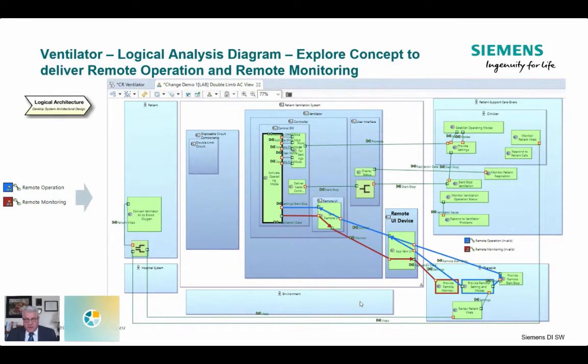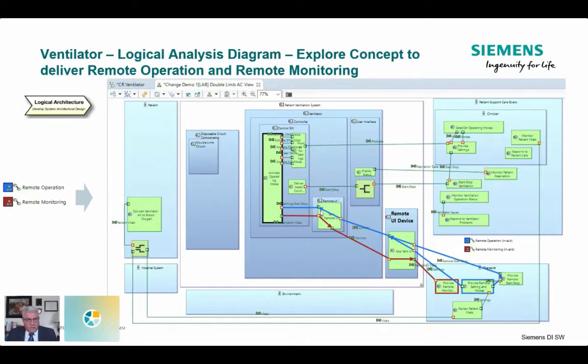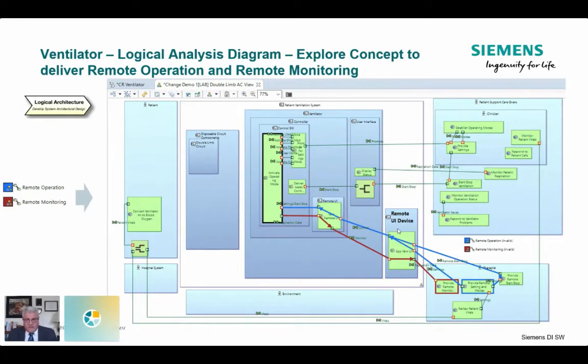Those system functional chains — remote operation and remote monitoring — now get detailed out across the logical components. I've introduced a new component called the remote UI inside the ventilator controller itself, which is a new behavior component that's going to be a new piece of software. I'm actually representing that piece of software and isolating it from the existing software, with hopes that when we go to the FDA we don't have to recertify the entire device. We're getting clear on what functionality is going to be in each thing. Then I'm depicting in this abstract logical architecture diagram the remote UI device that's going to be used, and denoting what are the processes that the therapist basically wants to do to implement this system.